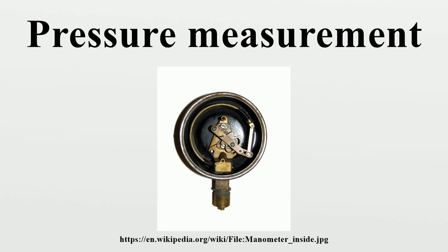Using atmospheric pressure as reference is usually signified by G for gauge after the pressure unit, e.g., 70 psig, which means that the pressure measured is the total pressure minus atmospheric pressure. There are two types of gauge reference pressure: vented gauge and sealed gauge. A vented gauge pressure transmitter, for example, allows the outside air pressure to be exposed to the negative side of the pressure-sensing diaphragm, via a vented cable or hole on the side of the device, so that it always measures the pressure referred to ambient barometric pressure.